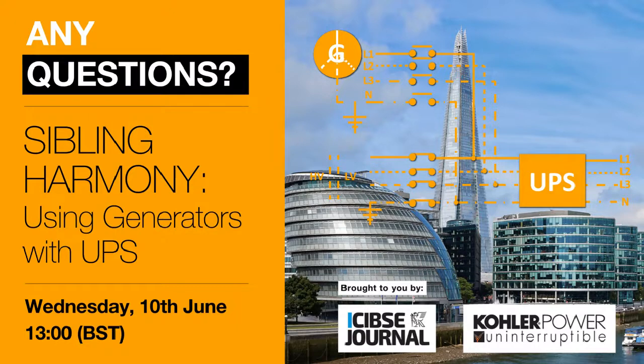It's a system designed for cleaning the fuel, because predominantly what happens is you put 24, 48-hour fuel tanks into the basement of a building, then you run a generator for 1 hour every so often on load, and the fuel can start to break down. So you can then clean the fuel and pull any impurities out of the fuel by using the fuel polishing system. Because leaving fuel stand for 12 months, 18 months at a time, even though you're only running 1 hour, which is taking a small amount of fuel from the tank, isn't good for the fuel.